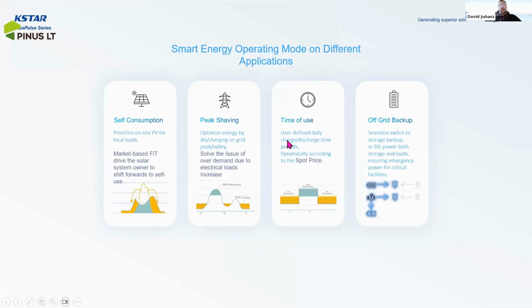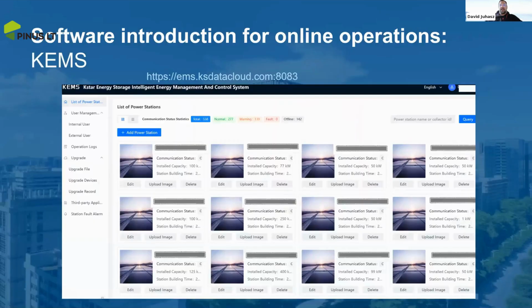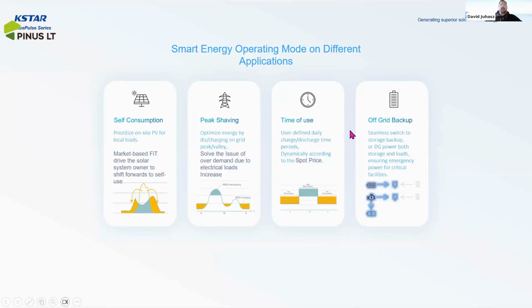And we have the time of use, where we can directly set the time periods when to charge or when to discharge the battery cabinets. This can be useful if the energy prices are connected to this, and the system can adjust itself dynamically for spot price controlling. And the last is the off-grid backup, which works so that the equipment always keeps some SOC level in any case, and this makes it possible that if there is a blackout, this capacity is always there to ensure the emergency power supply of the building.